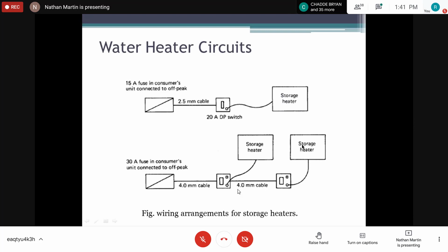If we were to connect two water heaters, we realize that we are using a larger breaker and a larger cable, and we are able to connect two water heaters, right? But if we're talking about a single water heater, then we're talking about 2.5 mm, and this is below the 15 amp, right? So below 15 liters, we can connect them like this. These are the typical arrangements that we'll use in our system.